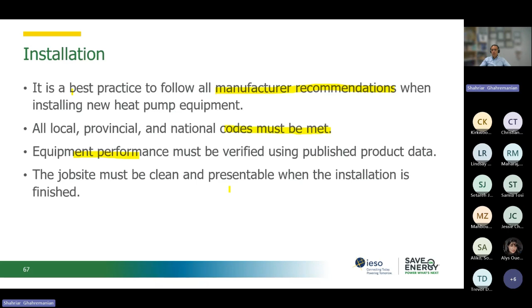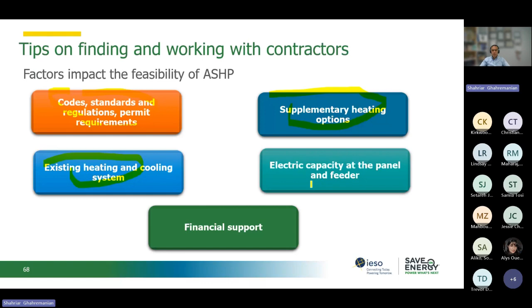Heat pumps are different from air conditioning and other systems, so we need a special place for them. A few tips on factors that impact feasibility: the codes, standards, and regulations we have; what existing heating and cooling systems are in place; whether we need supplemental heat and what kind; electricity capacity at the panel and feeder, since a larger electricity demand from the heat pump needs to be considered; and financial support or incentives if available. That was the presentation on heat pump applications.